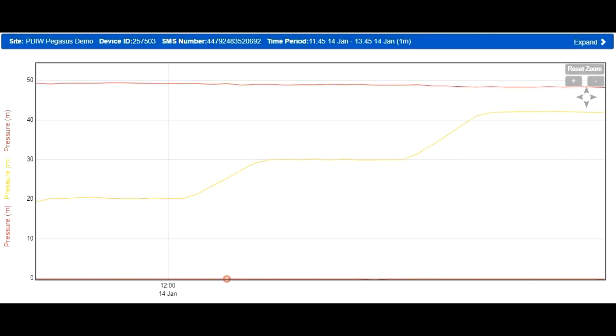In this graph, we are able to see two clear lines. The red line represents the inlet pressure or upstream pressure, and the yellow line represents the outlet pressure or downstream pressure. As you can see, and based on the previous configuration done through our PRV web platform, Pegasus is maintaining a pressure setpoint by increasing it over the time.